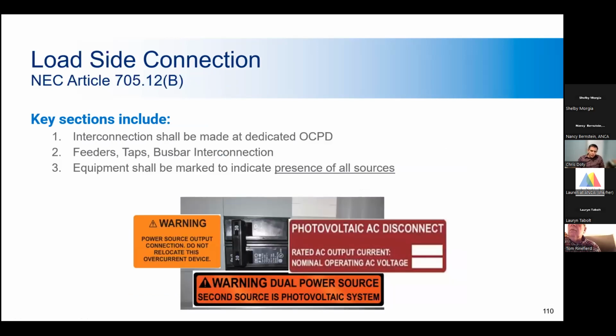These labels are required when the 120% rule is in effect, and it's used to add PV to the bus in excess of its rating. And like I said, this requires that the additional power being supplied to the bus is located at the opposite end of the bus so as not to overload the bus, as we've seen already.